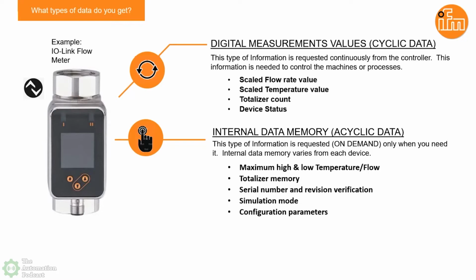We can put the sensor into simulate mode and put parameters in there, because sometimes you don't have flow going through the sensor during commissioning, but you still want to make sure the data and everything goes back to your PLC and your logic is correct, so you can put it into simulation mode.